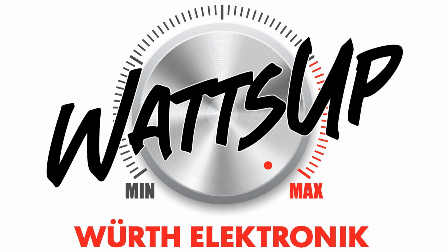Current transformers, while not as small nor as inexpensive as shunt resistors, are still quite small and relatively inexpensive, especially when comparing them to the electronic current transformer solutions, or the electronic current sensor solutions. The beauty of the current transformer is that they provide galvanic isolation, and the power dissipation is very low in comparison to shunt resistors. Another advantage of the current transformers is that they have a high output signal, which provides better noise immunity.